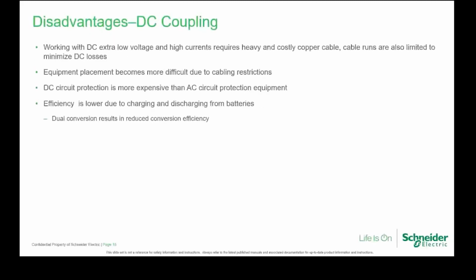However, it has some disadvantages, basically because you are working on extra low voltage. You need high currents for heavy and costly copper cable. Also, cable runs are limited to minimize DC losses. One thing about the XW Plus Pro is that they require decent sized DC cabling, otherwise the losses on the DC side can impact the operation of the XW. Equipment placement becomes more difficult due to cabling restrictions, so you've got to make sure that you've got enough room to bend the cables around to the XW. DC circuit protection is more expensive than AC circuit protection equipment. Obviously, you need bigger circuit breakers due to the higher currents.